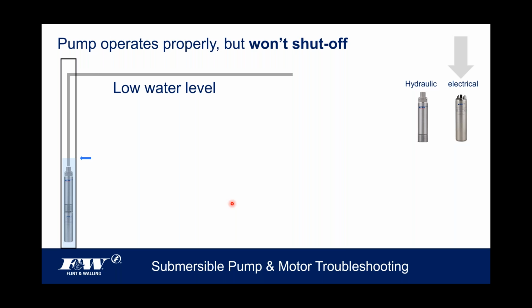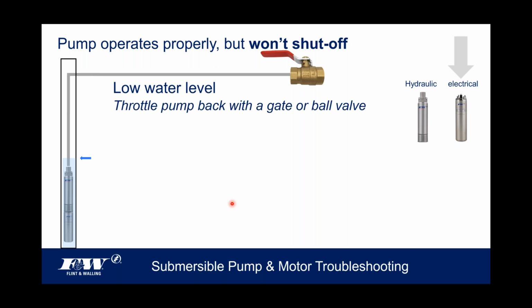They can get into some pretty severe drought situations. And wherever that may occur, you get a drop in the water level. All right, so when that water level drops, I'll tell you, the performance of that pump's going to fall off quickly. So one way of, again, sometimes these are just band-aids, but it gets the customer water, it gets the pump to shut off.